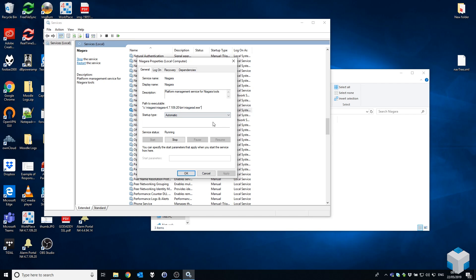It's running this executable here, which you'll note is currently 4.7.109.20\bin\niagarad.exe. That's the Niagara runtime environment. That's what allows a station to run on a system without user interaction, without workbench being open, without the system being logged on. It's what makes it start automatically.